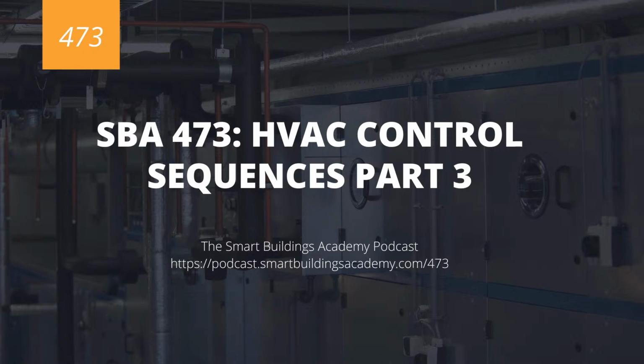All right, so what also we have, though, is CO2 control. And so ASHRAE 62.1 defines, based on space type and occupancy count, you must have a certain amount of fresh air within a space, and that's required. Now, what we learn with Economizer control is that we can utilize a CO2 sensor, and we can measure return air or space CO2, and then control our Economizer position in order to control the CO2 level of the space or the return airstream.